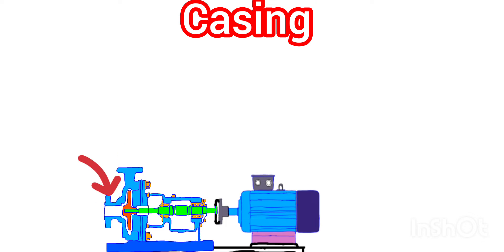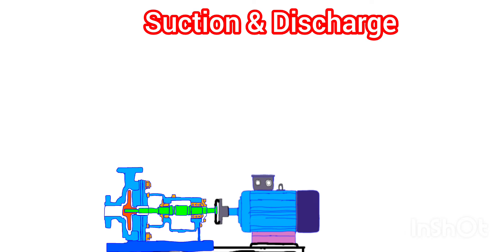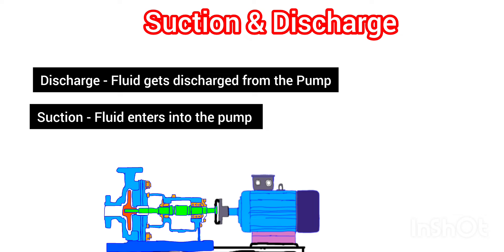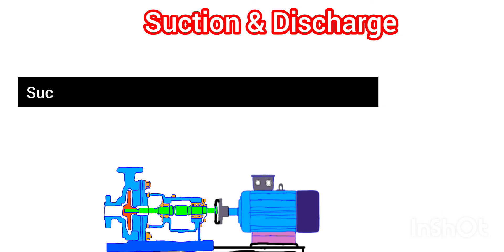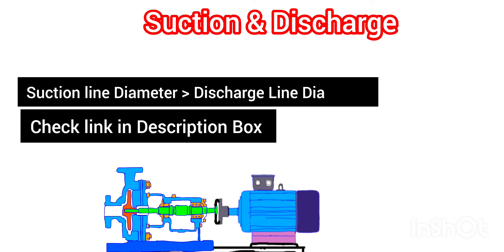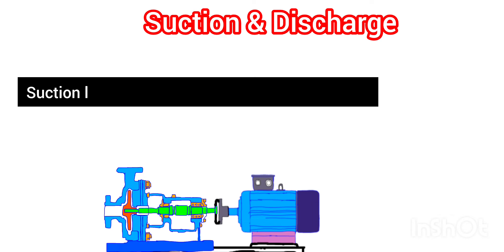The next component is the inlet and outlet of the pump — we call them the suction nozzle or suction side, and the discharge nozzle or discharge side of the centrifugal pump. From the suction nozzle, fluid enters into the casing or pump. From the discharge nozzle, fluid exits the pump or casing. We always design the suction size bigger than the discharge size — the main reason is to avoid cavitation. A link with more explanation is provided in the description box.